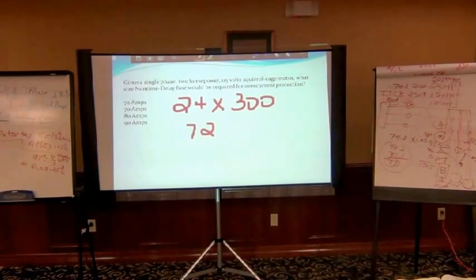So is that the answer then, number 1? Yeah. Well, it's an answer on the test, but it wouldn't be the right one, right? It wouldn't earn you any points. Down. Did it round down? Why round down? Yeah, because there's nothing in that test question that tells you that you have any permission to use exceptions, correct? And because of that, you'd have to round down, and the next size would be 70.